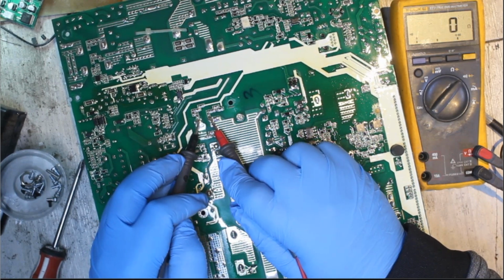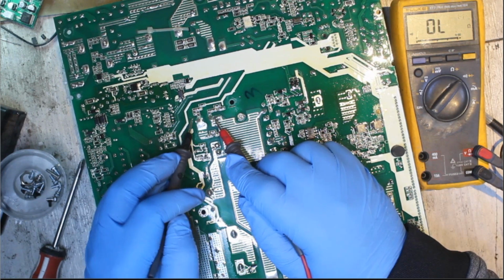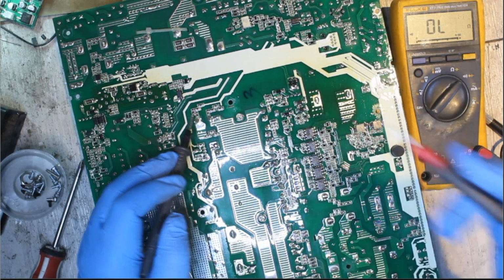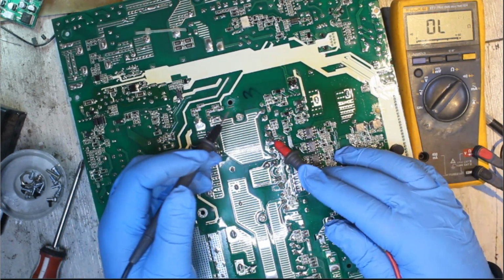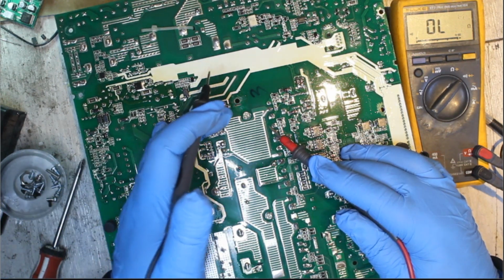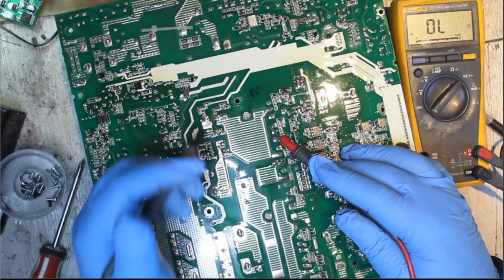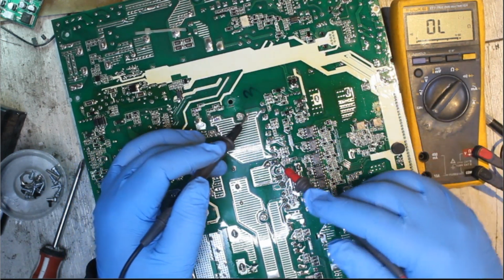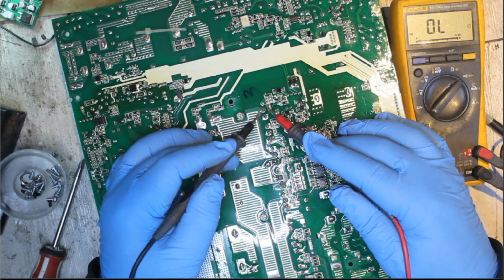So we are having a short circuit there. That's why we are having F09. So that's the first thing that we have to check. If we have a short circuit on the big capacitor, obviously we're gonna have an F09 because the inverter is trying to charge the capacitor, but the capacitor is dead short circuit, it's not charging. Then it will just throw that alarm F09. Let's check the transistors.